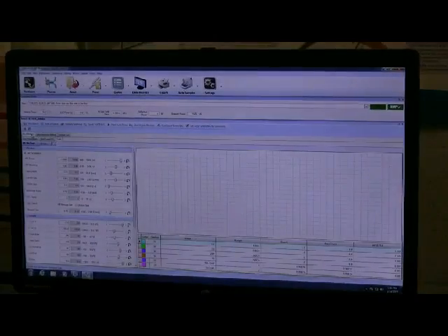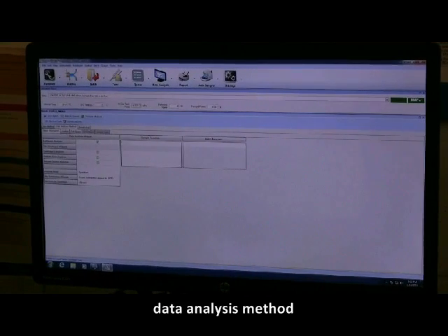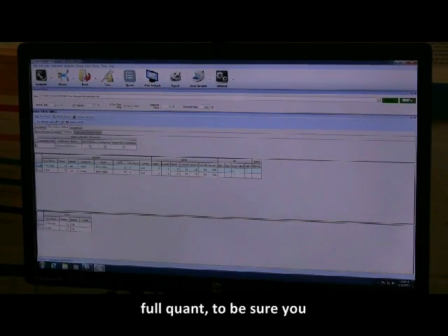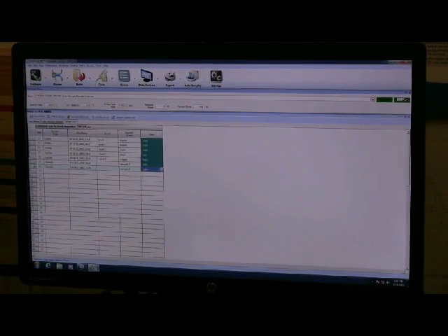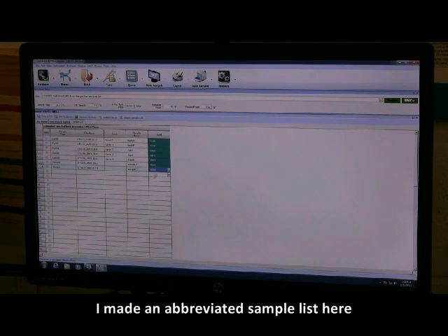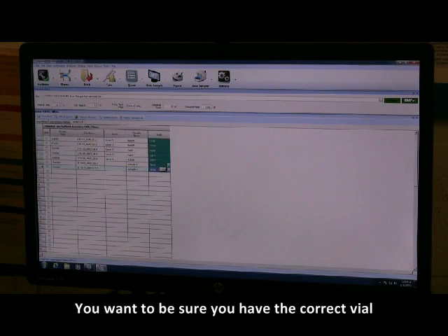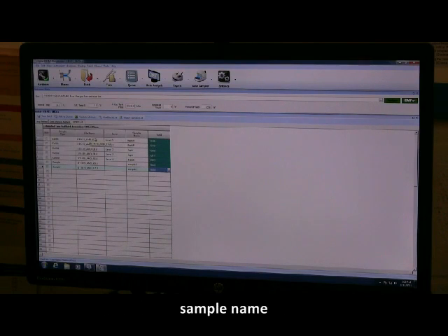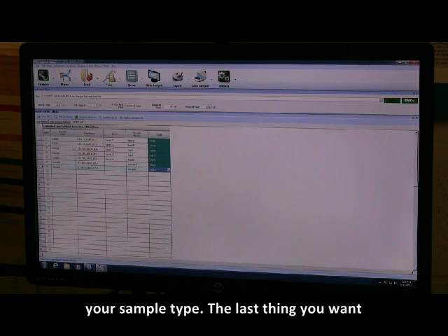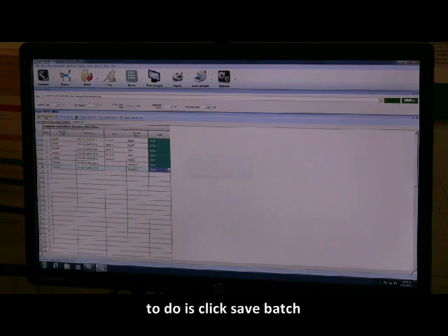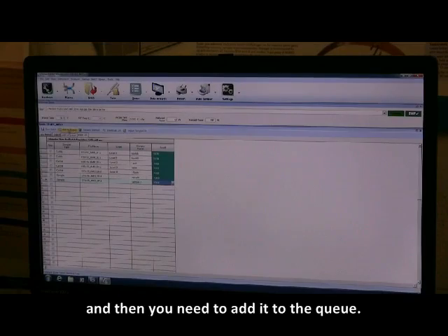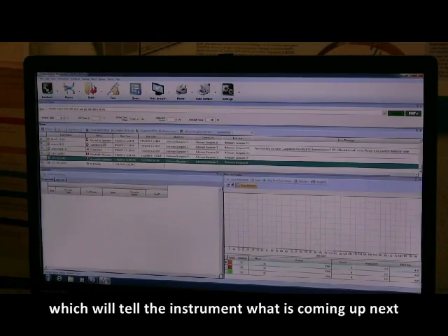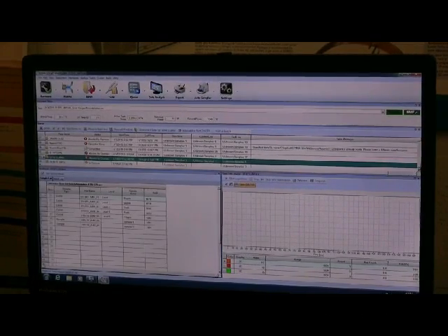You can double check your data analysis method, full quant, to be sure you have the correct levels. Double check your sample list. I've made an abbreviated sample list here. You want to be sure you have the correct vial, the sample name, your file name, your levels, your sample type. The last thing you want to do is click Save Batch, and then you need to add it to the queue, which will tell the instrument what is coming up next.